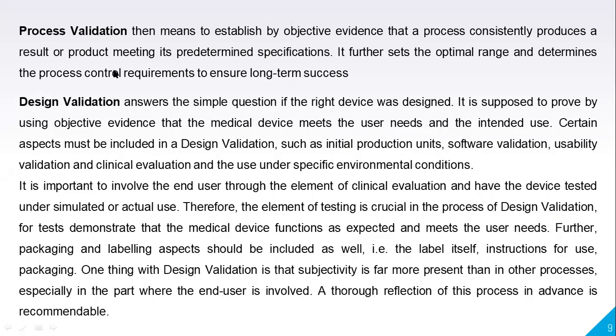Then similarly, there will be another step called design validation. It also answers a simple question: was the right device designed? Why is design validation needed? If the right device is designed and also manufactured, it is supposed to prove, by using objective evidence, that the medical device meets the user needs and the intended use. Certain aspects must be included in a design validation, such as initial production units, software validation, usability validation, clinical evaluation, and the use under specific environmental conditions.